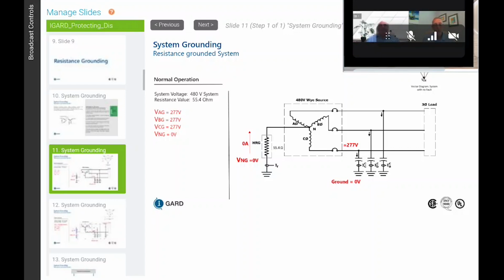The only difficulty I could see might be if the fault current is only going back through one phase. But if you're saying all the concentric neutrals are tied together to ground, then there's multiple paths for that current to take back to the source. You heard the expression that current takes the path of least resistance. It's not true. Current takes every single path that's available to it. And the more grounds you have, the more paths that current has to get back to the source. Here, all these paths go back to the source. So you have an entire network here.